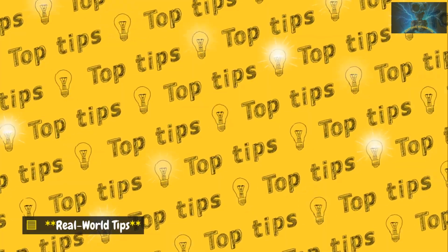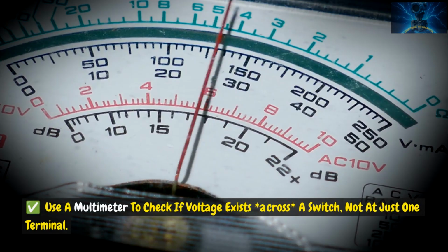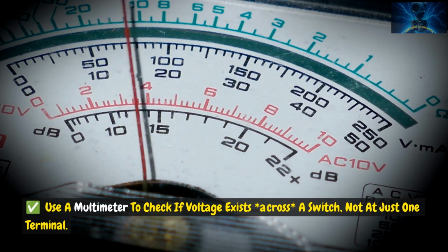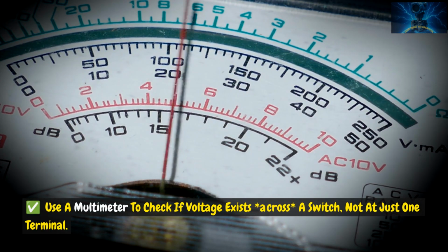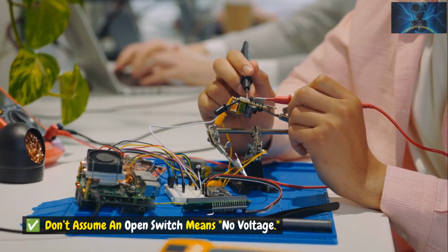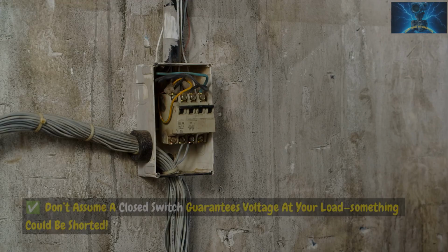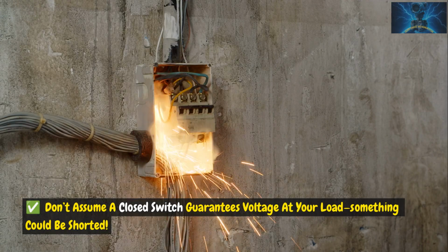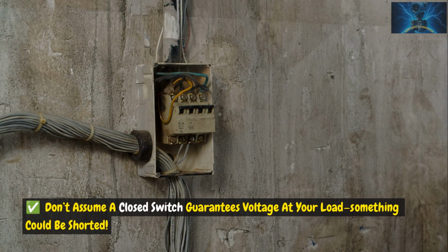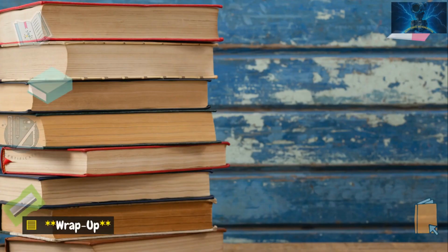Real-world tips. Use a multimeter to check if voltage exists across a switch, not at just one terminal. Don't assume an open switch means no voltage. Don't assume a closed switch guarantees voltage at your load. Something could be shorted.